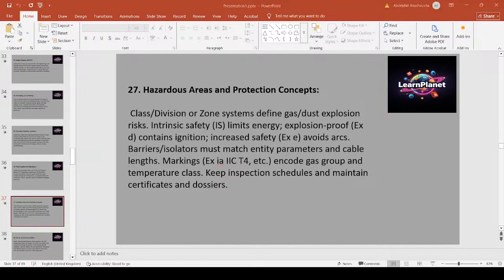Class division or zone systems classify hazardous areas. Select equipment with the appropriate Ex marking. Intrinsic safety limits energy in the circuit. Explosion proof contains an ignition in enclosures. Increased safety means improved design to avoid arcs. Match barriers and isolators to the device, entity parameters, and cable length to maintain IS approval. Maintain dossiers and inspection certificates and schedule recertifications. Example: where a sensor in zone 0 is required, use an Ex ia rated transmitter and IS barriers in the marshalling cabinet.